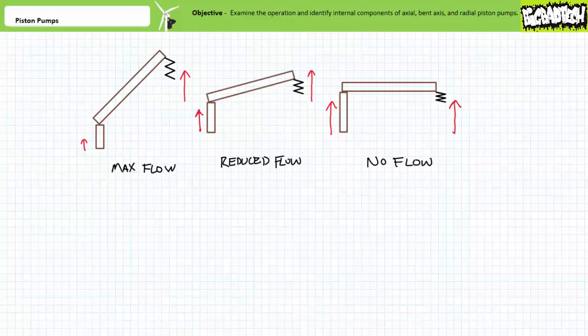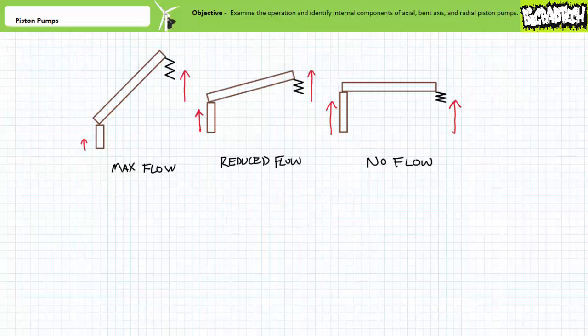Some textbooks depict variable displacement piston pumps with a maximum negative angle as having no flow — this is wrong. A swash plate held at a maximum negative angle would produce maximum reverse flow. Additionally, the spring and piston pair is not the only method used to vary the angle. Some advanced variable displacement piston pumps use solenoids, a type of linear electrical actuator, to electrically position the angle of the swash plate with great accuracy and control.